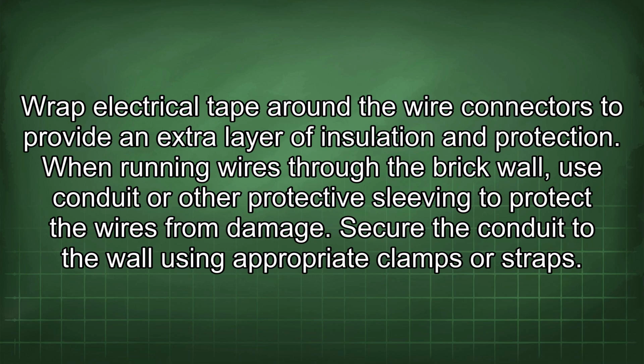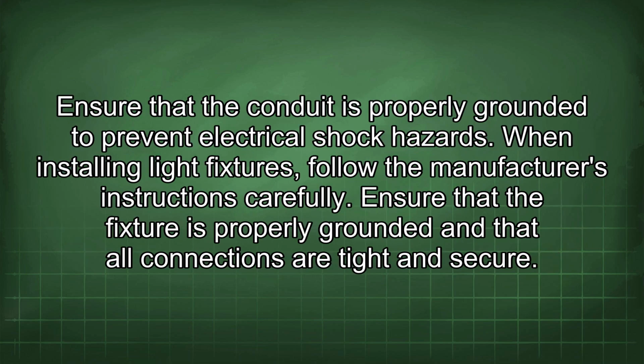When running wires through the brick wall, use conduit or other protective sleeving to protect the wires from damage. Secure the conduit to the wall using appropriate clamps or straps. Ensure that the conduit is properly grounded to prevent electrical shock hazards.